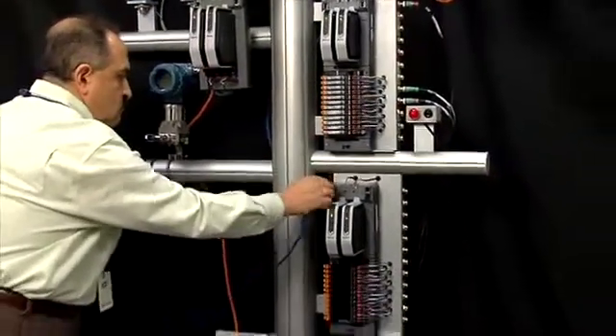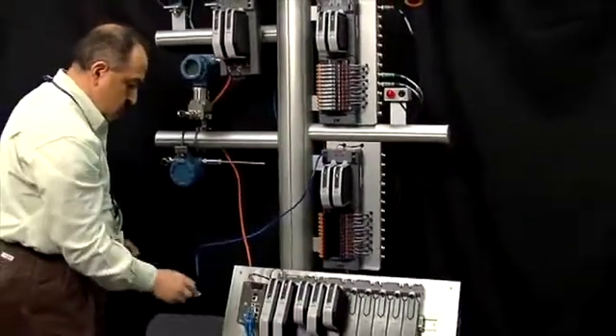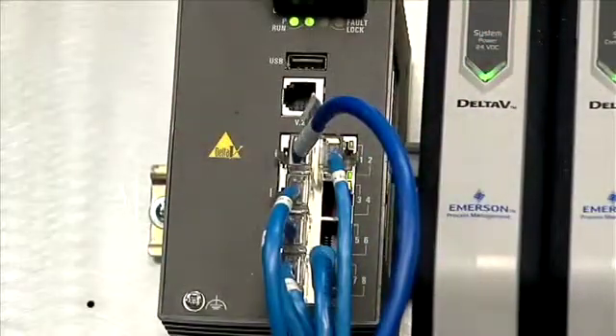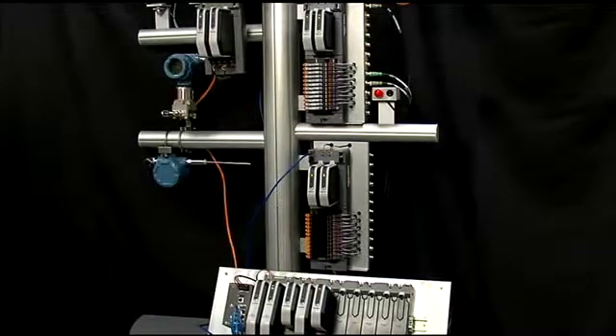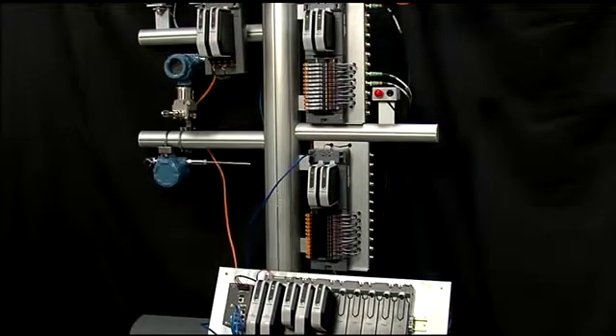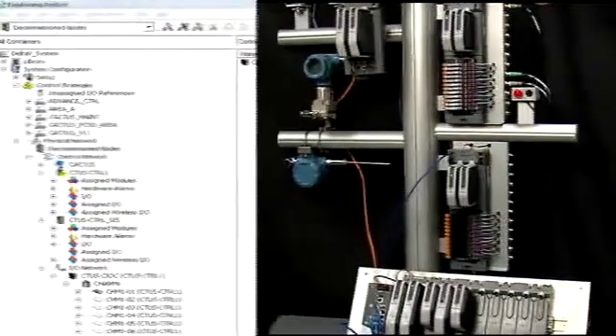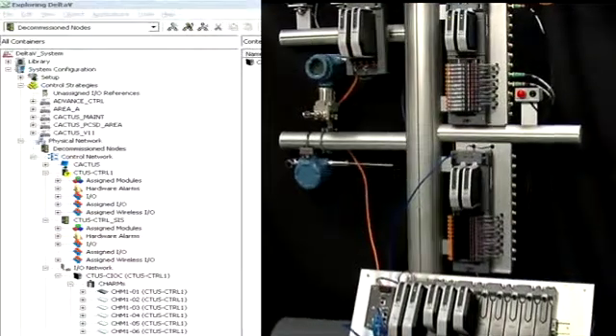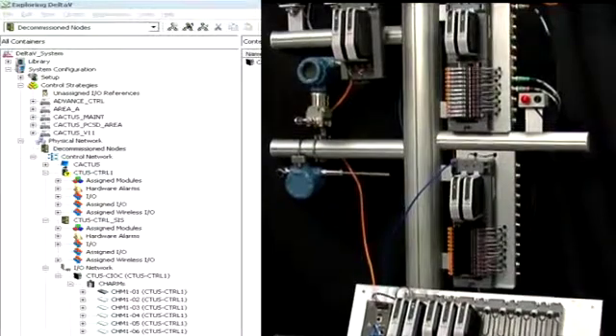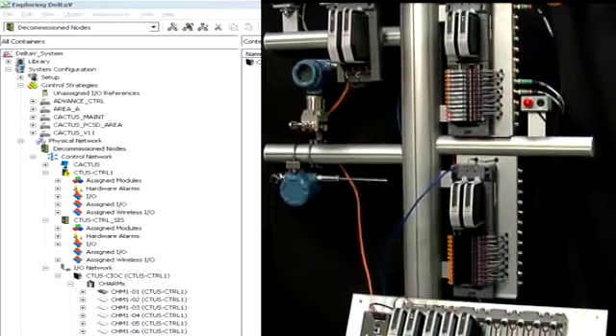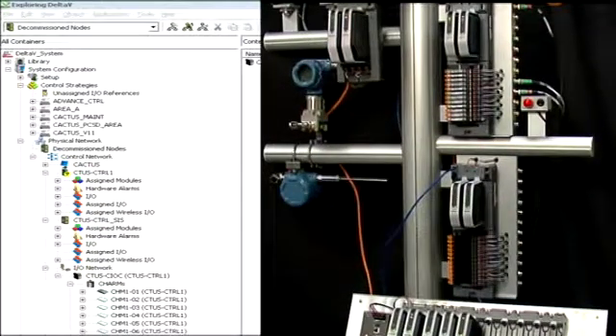Notice that in this case, we are also connecting the CIOCs to the control network using Ethernet cable and connecting directly to a network switch. It's important to note that throughout the online addition of the new CIOC, the rest of the Delta V system remained running and unaffected as shown here.